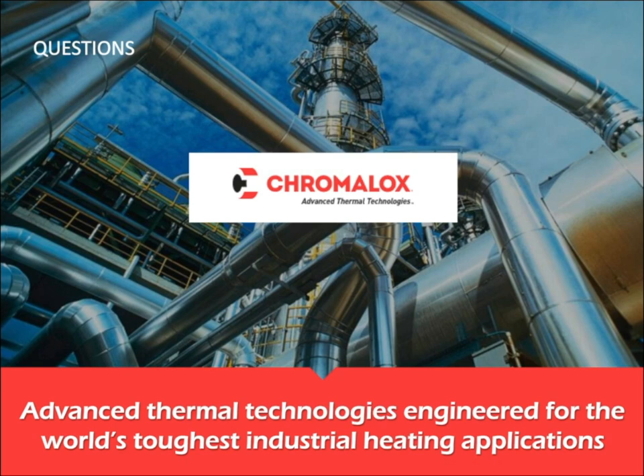Also, another question here. Can a medium voltage system be located in a hazardous area? Oh, yeah, good one. Electric heating in general lends itself to providing very localized heating, so that the source of that heat can be located directly in a hazardous area. With a fuel-fired system, generally you're not going to want an open flame in such an area, or places like a refinery or an offshore platform can cause some issues. So you'd want to have that system located far away. But with electric heating, both low voltage and medium voltage, it can be located directly in an area.